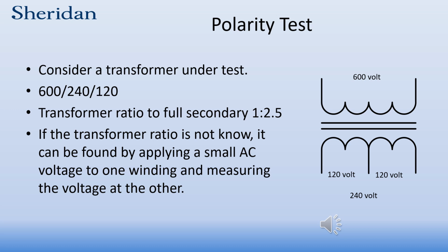It's a 600 to 120, 240 volt. The transformer ratio is 1 to 2.5. That is 600 to the 240 volt. If the transformer ratio isn't known, it can be found by applying a small voltage to one winding and measuring the voltage at the other. You should always apply your test voltage to the high voltage side.